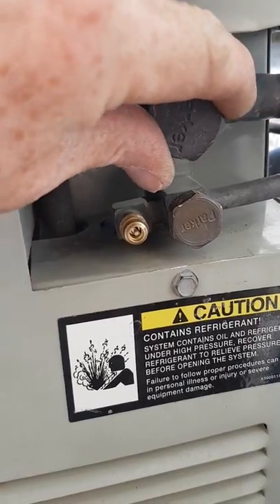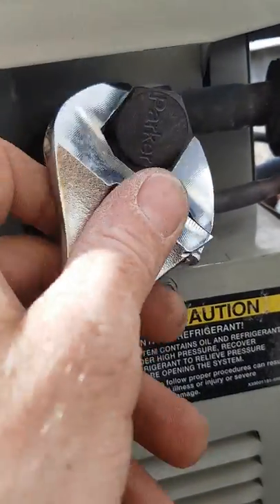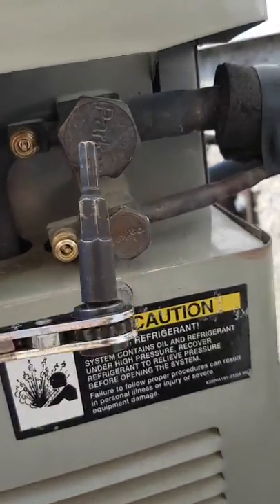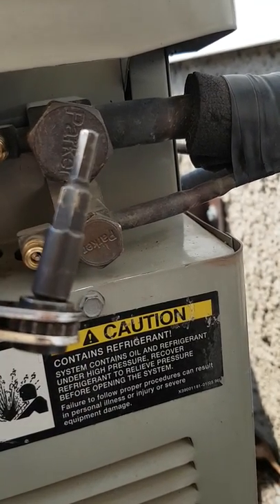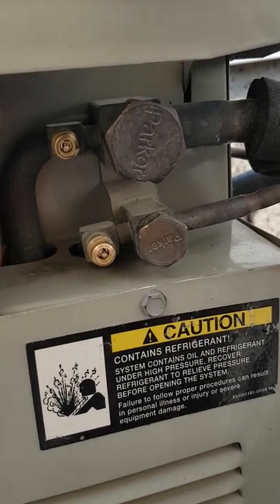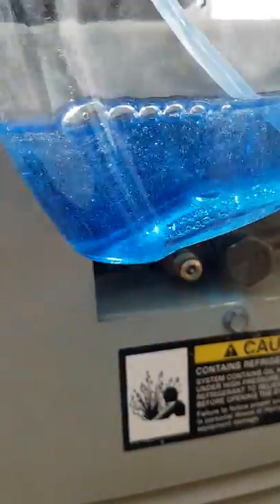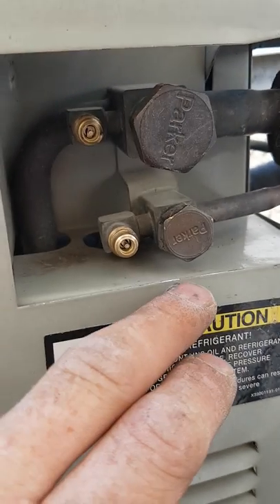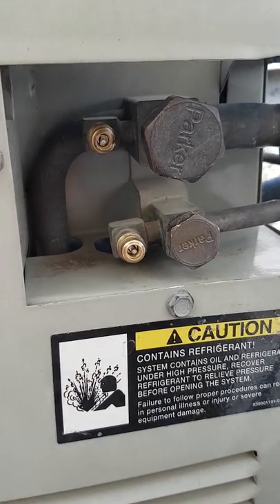The next thing I like to do is take these service valve caps off and make sure there's no little hiss of refrigerant when I do. I also like to take my service wrench — I've got this nice Hilmor adapter that goes in my service wrench, which really helps and makes the process go quicker. I like to backseat those, then use a little Cal Blue leak soap — nice thick stuff with big bubbles. I soap that service valve before I put the cap back on to make sure the gasket in that service valve is not leaking.